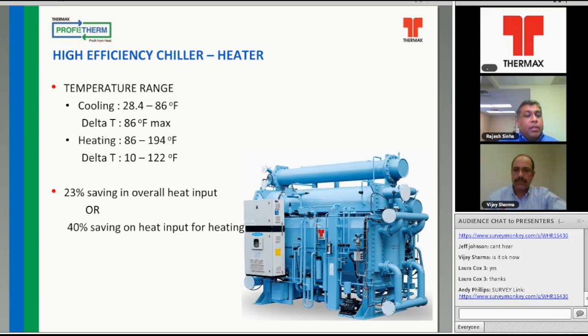The temperature ranges are as follows, for cooling and heating. This particular product can entail a 23% saving in overall heat input over a standard two-stage absorption machine, or it can have 40% saving in heat input for heating.